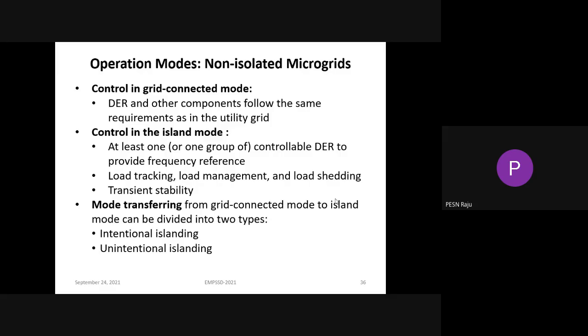Grid mode to islanding mode transfer can be either intentional or unintentional islanding. Intentional means that when there is some grid failure, we open the switch between the microgrid and the point of common coupling. Unintentional means it is not the expected one, and we should implement automatic opening of that smart switch when there is some failure in the main grid. Coming to the grid-connected mode, the entire microgrid will act as a controllable source or load, and all components will follow the same commands given by the utility grid.